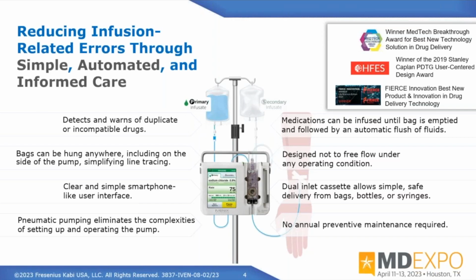What that buys us is we know consistently the pressure we're applying in that chamber, and we can measure against that. So if I'm measuring my flow here, I'm controlling the infusion very accurately. And then in order to level out those spikes and troughs that can occur with an infusion, I'm actually controlling the infusion with a dial here. So this little armature here will control the dial during the infusion and flatten out those spikes and troughs. And we've got a graph to show you that as well.